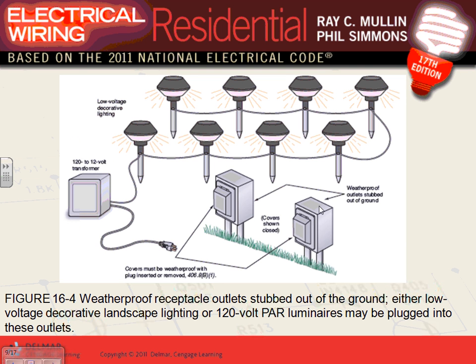So, Rob, my friend, if you are to do a system like this, here's what you need to understand. Number one, you have to have a wet location enclosure, in-use cover, weatherproof GFCI receptacle, weatherproof, tamper-proof, because it's also in a residential, tamper-proof, and that's it. And then the whole system here, you buy it, guys, and you assemble these. You assemble them hot to hot, neutral to neutral, and you plant them wherever they are, and they don't have to be directly buried. They're 24 volt. I think there's a requirement for 6 inches, I believe, or so for them. Any question, guys, about this?